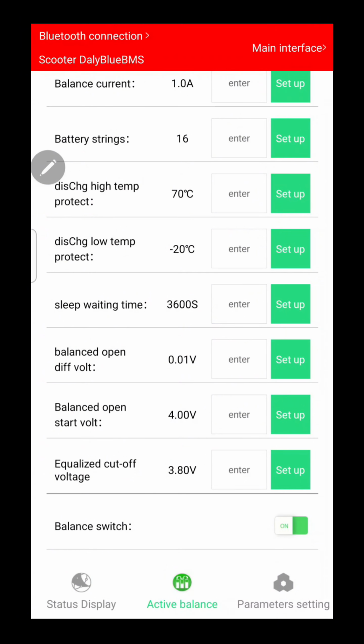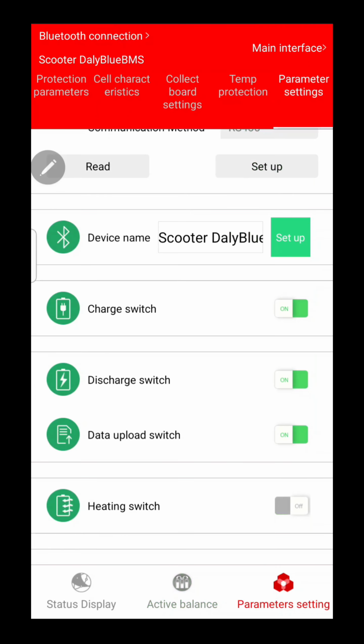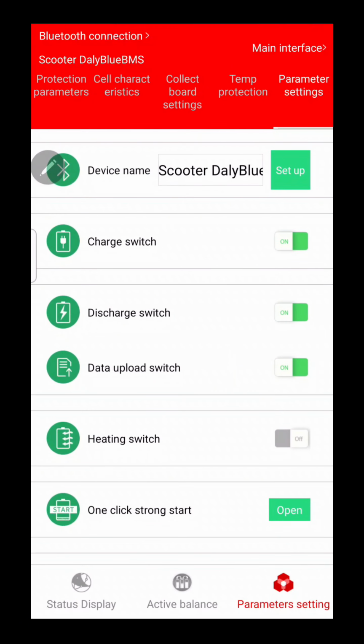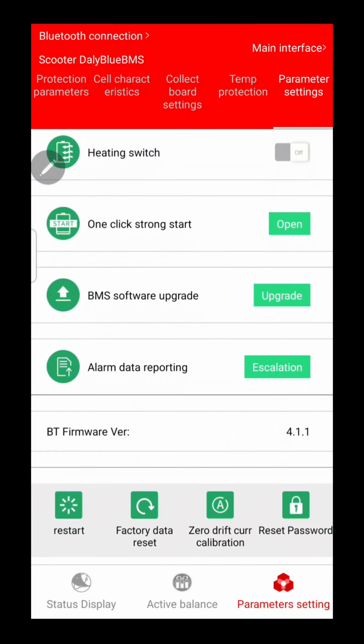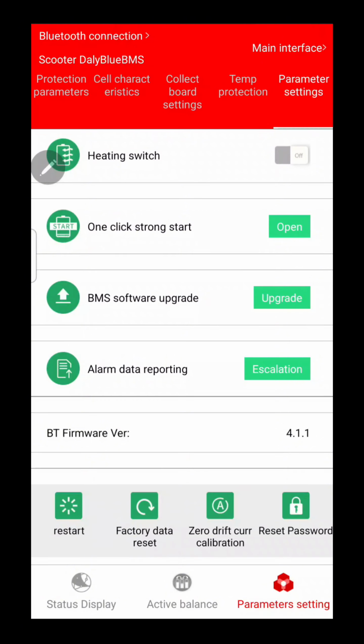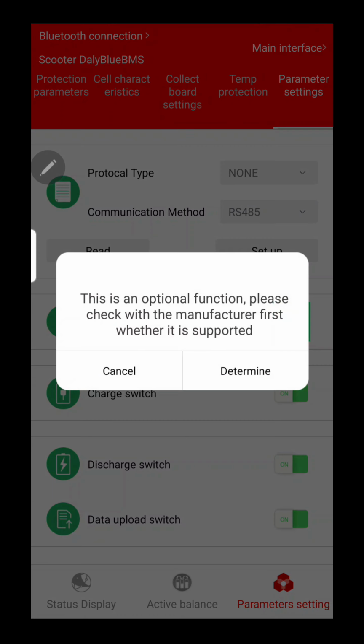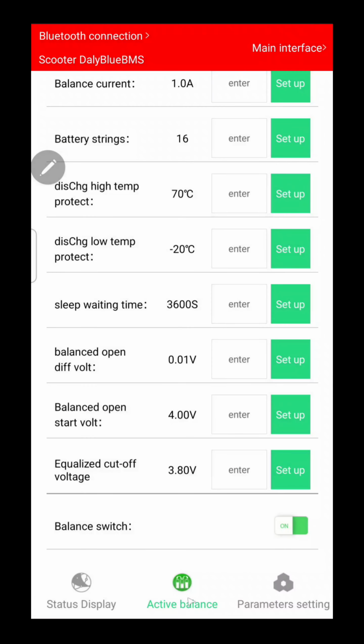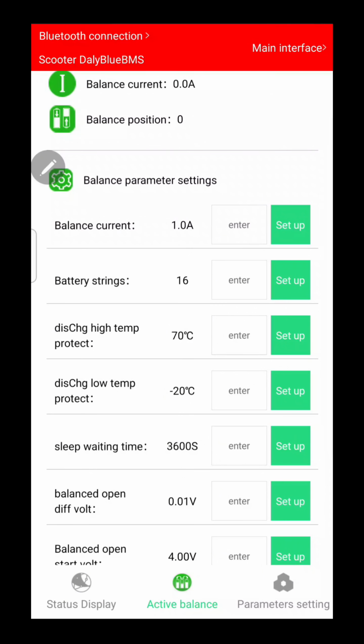This is really, really good. If anything happens to one string, say it goes to a high voltage for some reason, even if you're not connected to the charger, the balancer will come in and bring that back. The other parameters are basically the same as the normal Red Smart BMS - you've got your charge switch, discharge switch, data upload switch, heating switch, and all the other functions are basically the same. The big difference is having the active battery balancer parameters that you can set.